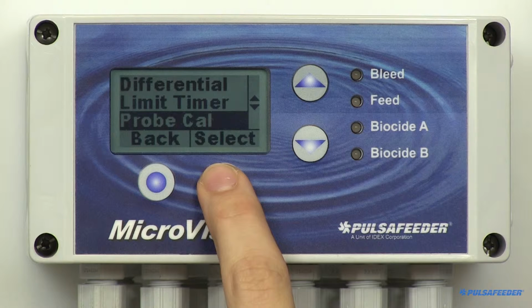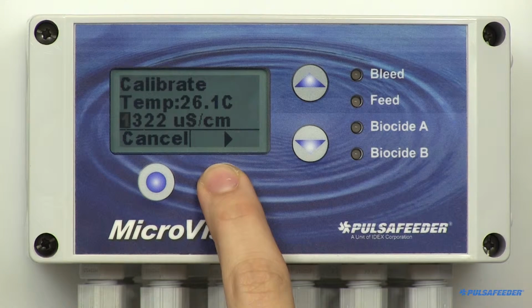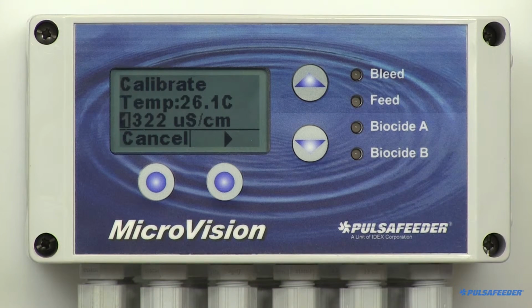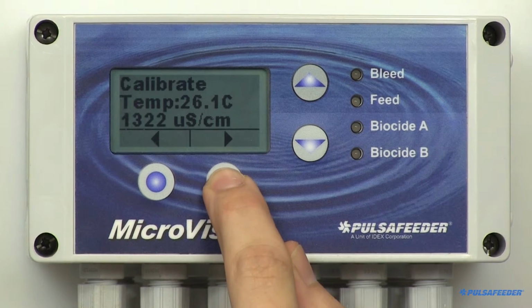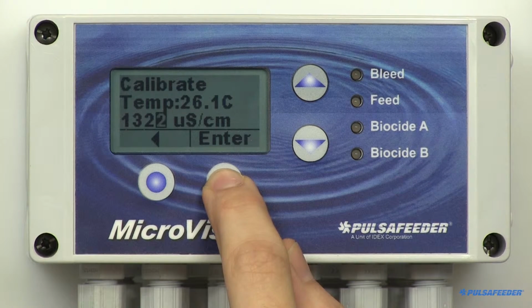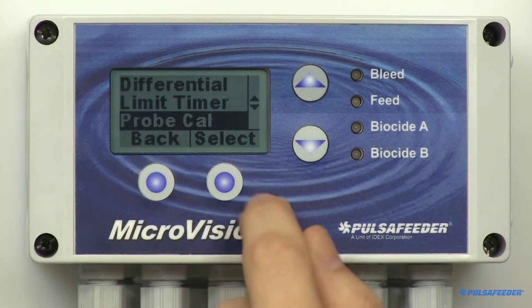It's always a good idea to calibrate your probe as close to the set point value as possible for accurate control. From the conductivity menu, arrow down to the probe cal and select it. You will see the probe's temperature displayed and the conductivity value in microsiemens. Use the arrow buttons to enter the current conductivity value, then hit Enter and OK.